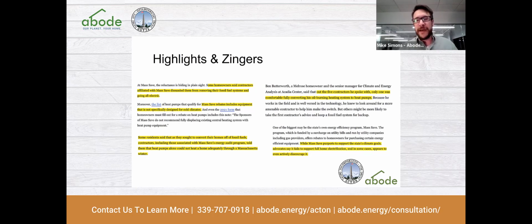Here's another issue: Mass Save rebates include equipment that isn't specifically designed as cold climate heat pumps. Mass Save is incentivizing heat pumps that may have 100% of their capacity at 50 degrees, but only half their capacity at 17 degrees, which is problematic because you'll end up relying on your fossil fuel system instead of the air source heat pump.